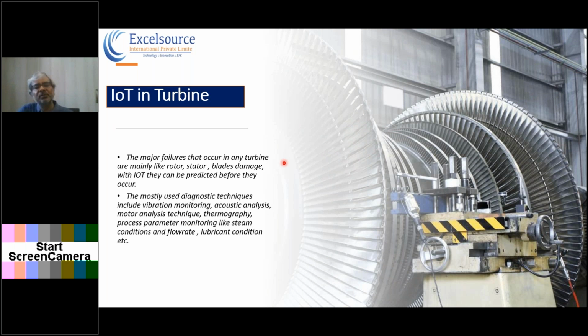The same thing can be implemented on turbines. What we have optimized is the cogeneration. How is it going to help us? It is going to help us get more power generated out of the turbine. We have to see if it is a condensing mode turbine or a partially extraction cum condensing mode turbine. We have various temperature sensors installed on heat exchangers, and we monitor the heat exchanger conditions, fouling conditions, and the approach of the heat exchanger between the steam entering the condensers and the water coming in and going out of the heat exchangers. This will generate more power.